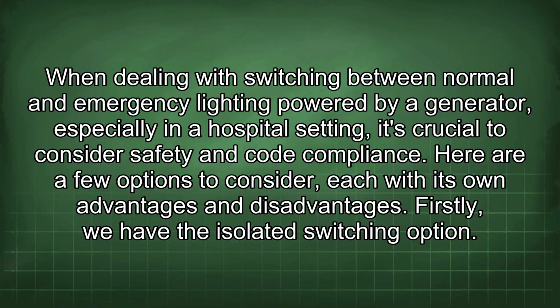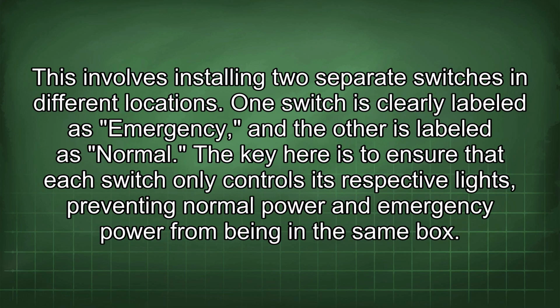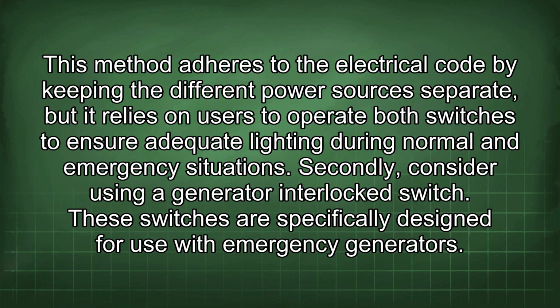Firstly, we have the isolated switching option. This involves installing two separate switches in different locations. One switch is clearly labeled as emergency, and the other is labeled as normal. The key here is to ensure that each switch only controls its respective lights, preventing normal power and emergency power from being in the same box. This method adheres to the electrical code by keeping the different power sources separate, but it relies on users to operate both switches to ensure adequate lighting during normal and emergency situations.